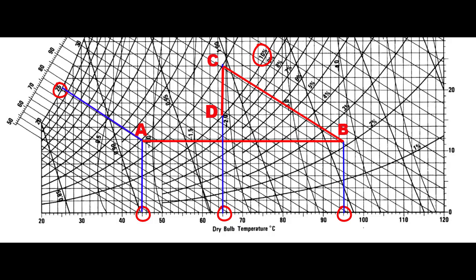We can read the values of humidity ratio on the right-hand side of the chart. For point C it is 24 grams of water per kilogram of dry air, for point D it is 16, and for point B it is 11.7 grams of water per kilogram of dry air. One more value we need is the specific volume for ambient air at point A. The adjacent specific volume lines are 0.9 and 0.95, so we estimate the specific volume at point A as 0.92 cubic meters per kilogram dry air.